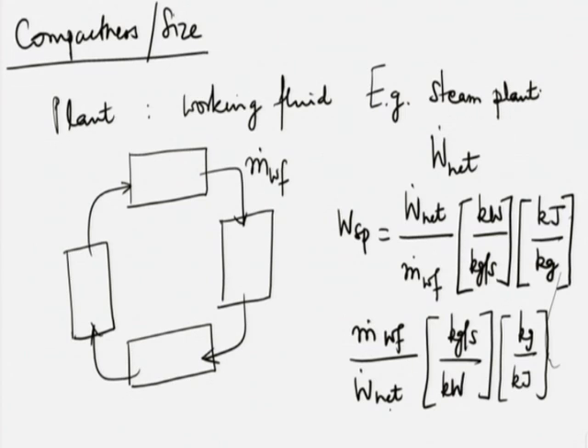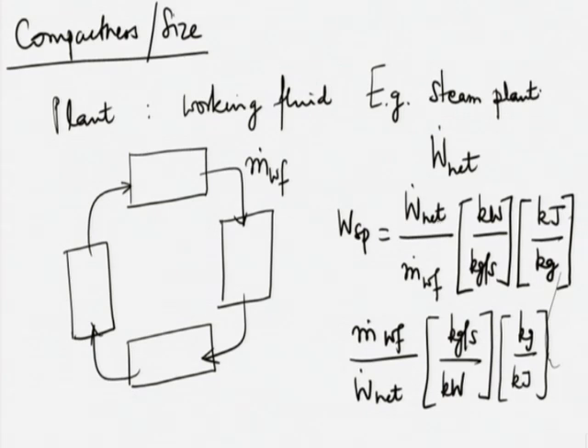If specific output is higher, that means for the same working fluid flow rate I take more output from the plant, or for a given output I need to circulate less fluid. This fluid is not consumed, only circulated. If you need less fluid circulated, that means smaller sizes of equipment — smaller duct sizes, smaller boiler sizes. Something with a smaller steam rate or a higher specific output will be a more compact plant. This has nothing to do with efficiency; it has to do with compactness of the plant.